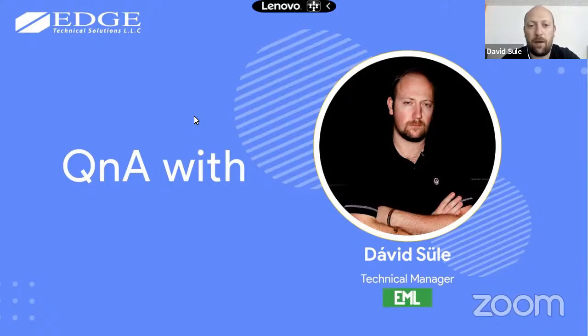Okay, thanks for the question. For programming the system, we need a physical hardware key with the programming software on your laptop. To add any new light or change faulty lights, we have to use the programming software only, with a physical hardware key. From the LCD screen, we can check only the last test results. We can check which light has a fault, but we can't program anything from the screen, it's just checking information. So programming software is needed to change a light and add a new light during maintenance.